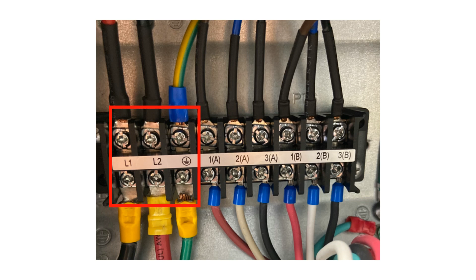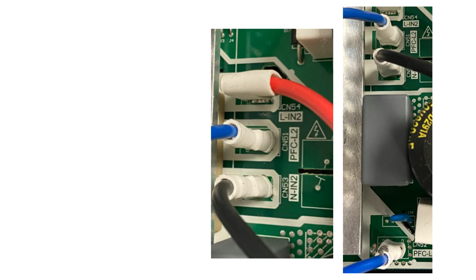If they are connected tightly but connection isn't normal, check whether the voltage range of PN on IPM module is normal. The voltage range on the 18K and 27K models should be 277 to 356 volts DC, and the voltage range on the 36K model should be 277 to 410 volts DC. Test these two ports, PFCL2 and PFCL, marked with blue wires and white plugs. If they are normal, then replace the outdoor main board.